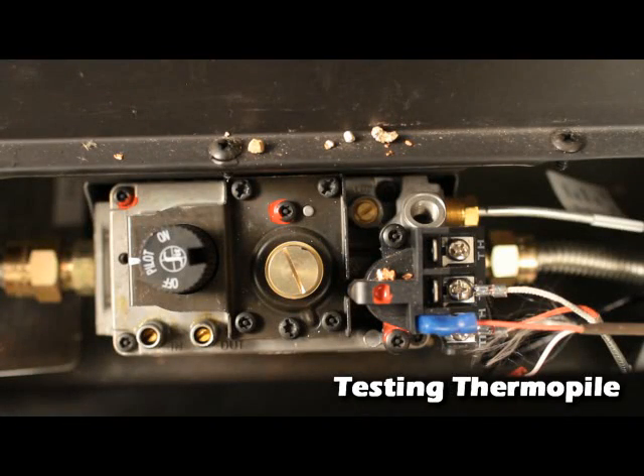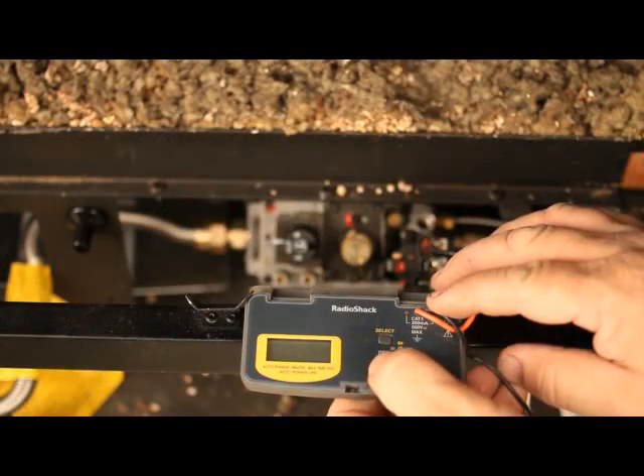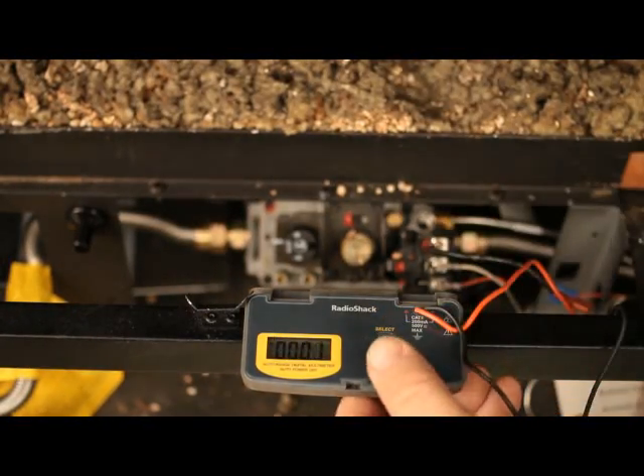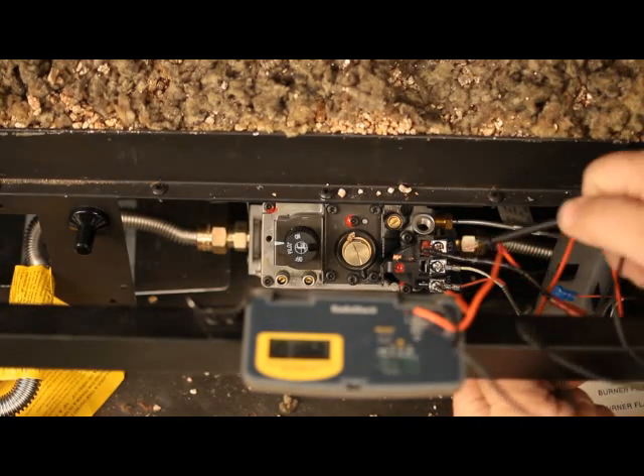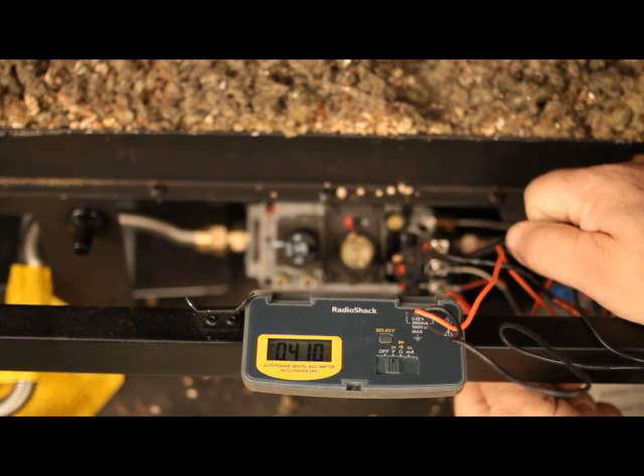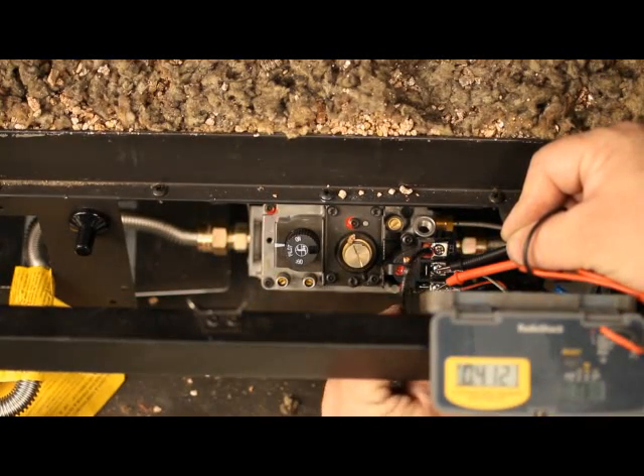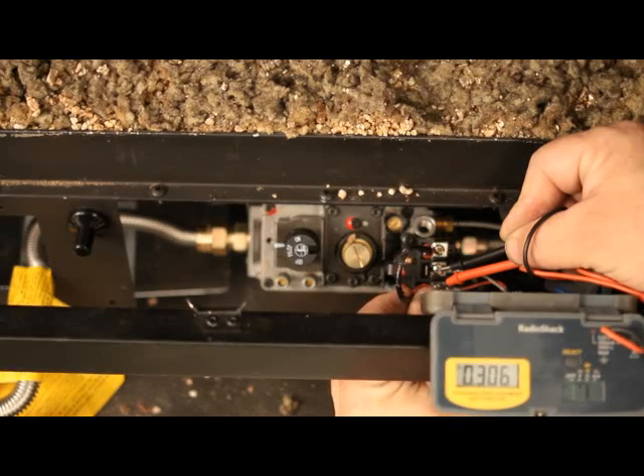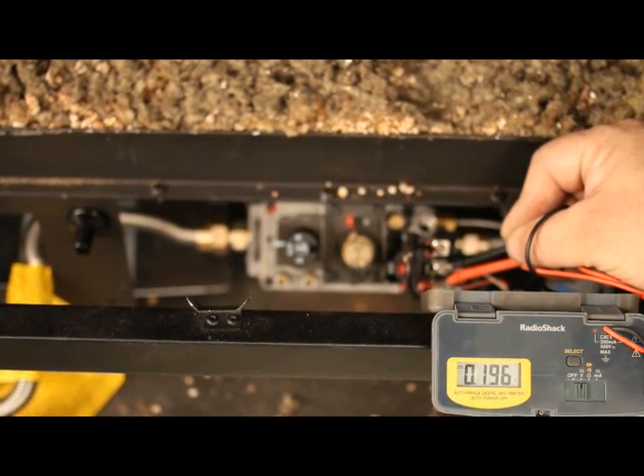Testing the thermopile. With the pilot lit and the burner off, set your multimeter to the DC setting or millivolt setting. Place one probe on the terminal THTP, the other probe on the terminal TP. Millivolts generated should be 325 minimum; generally readings will be 400 to 700 millivolts. Record your readings. Keep the probes on the terminals and turn the appliance on — millivolts will typically drop in half. 150 millivolts generated should be the minimum.